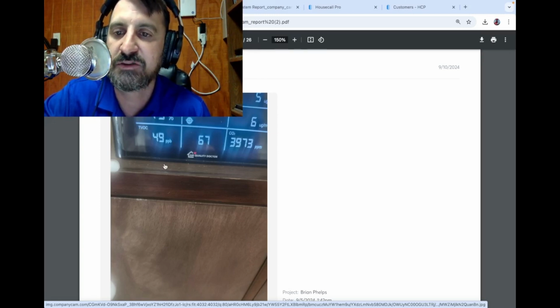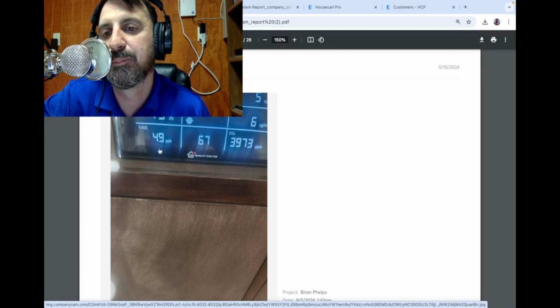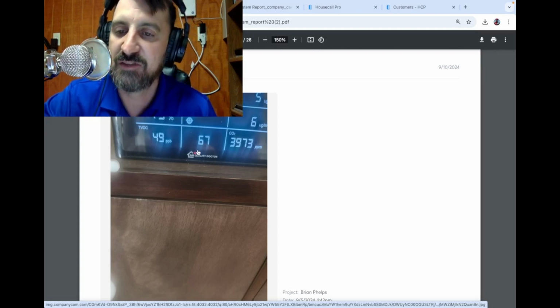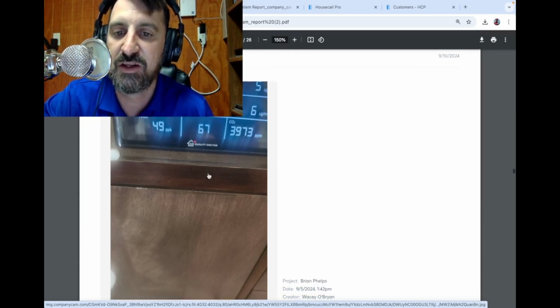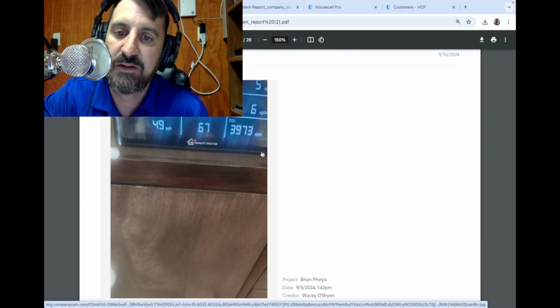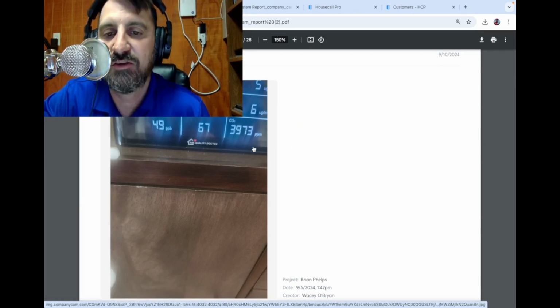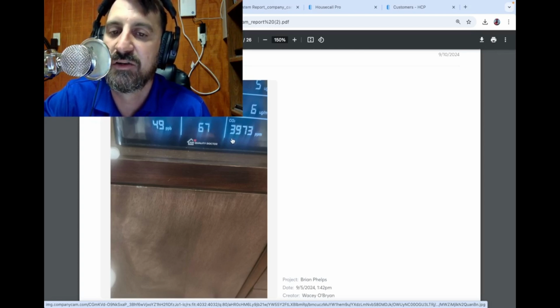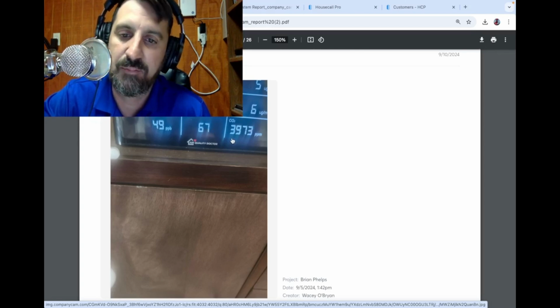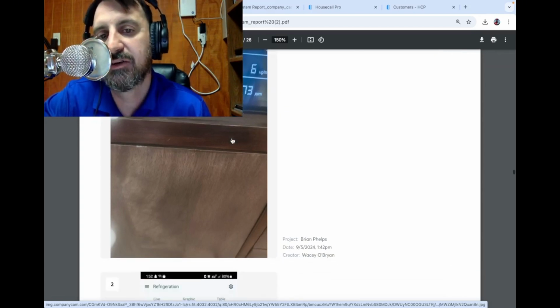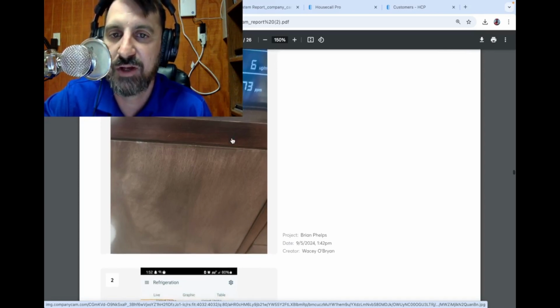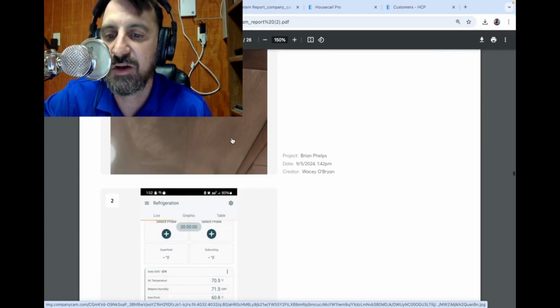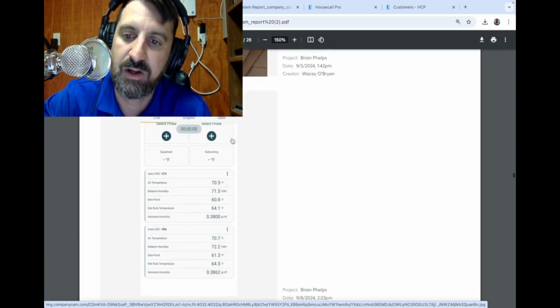This number, your temperature number, matters. But really, if your humidity isn't around 50%, it's not going to feel like what you think 67, 68, 69 feels like. And then you can see their CO2 levels. Generally, you want 1,000 to 2,000. A lot of statutes say 1,000 or under. I mean, going by the book, 1,000 or under. If it was at 2,000, I wouldn't panic. But anything over 2,000, you're getting pretty high.